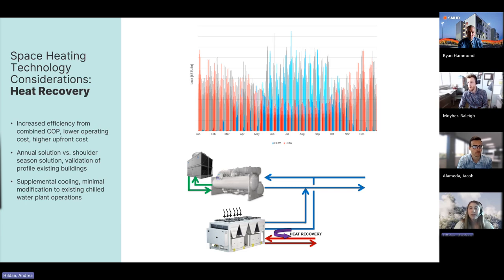And what I think is really cool is technology like the 4-pipe air-to-water heat pump has the opportunity to operate in either or mode, meaning when there's no simultaneous cooling, these units can operate in heating only mode, and then in those shoulder seasons, take advantage of simultaneous load and operate in heat recovery with the same piece of equipment.